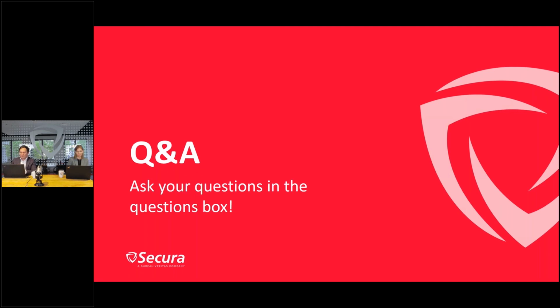That's a good one. In principle, the product should be free from high-risk vulnerabilities. This is the reason the UL 2900 standard also asks for vulnerability scanning and demonstrating results that the product is, as much as possible, free from vulnerabilities.